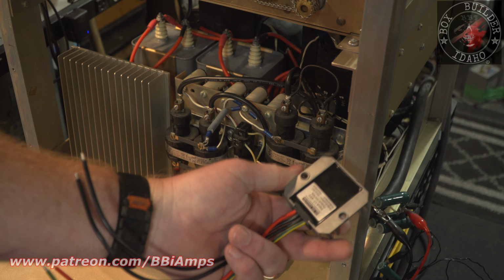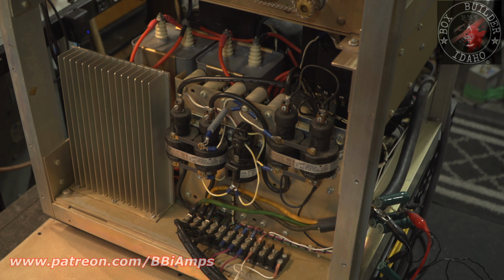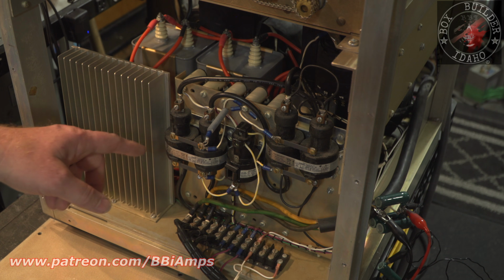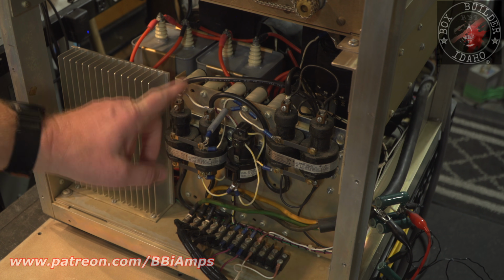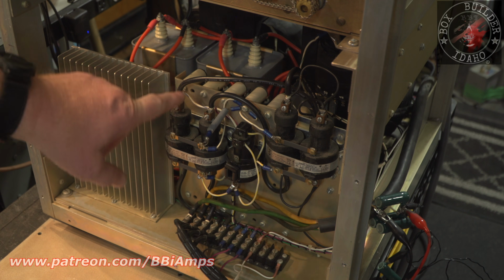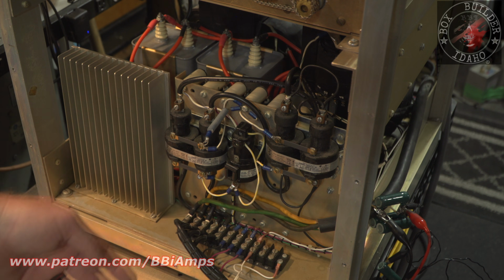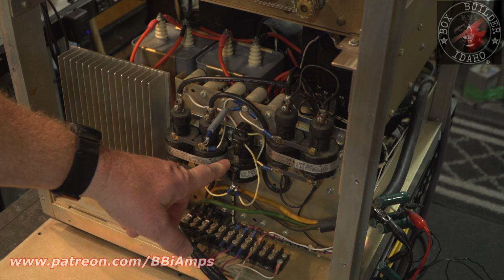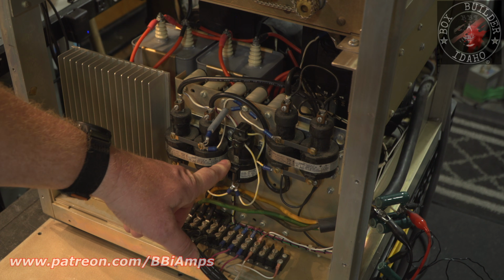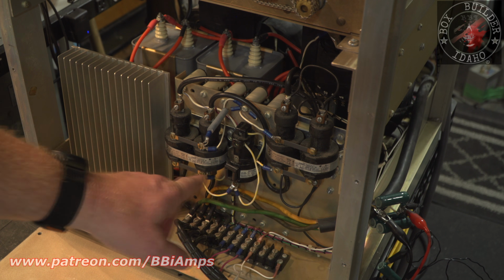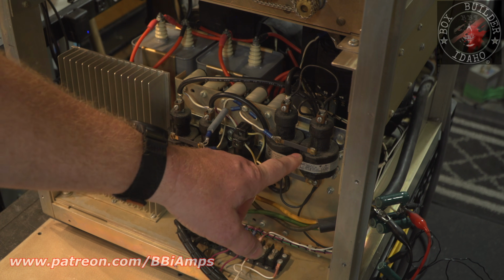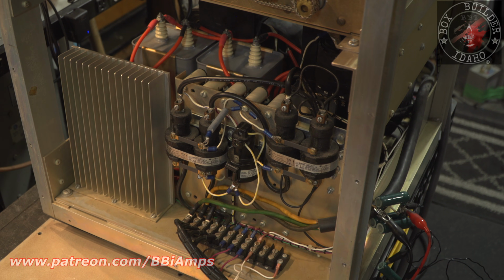This is the easiest fix. And maybe the time that it takes the electrons to spool up in the coil of this contactor and it closes, and then let's say 100 milliseconds or 50 milliseconds later, when the current spools up in this contactor and it pulls it shut, and then the electrons can rush and spool up in the coil of this contactor and it shuts and it bypasses the soft start.